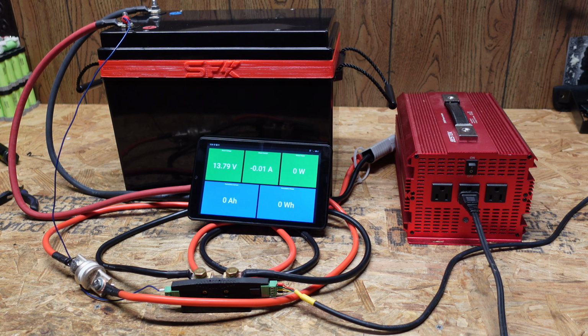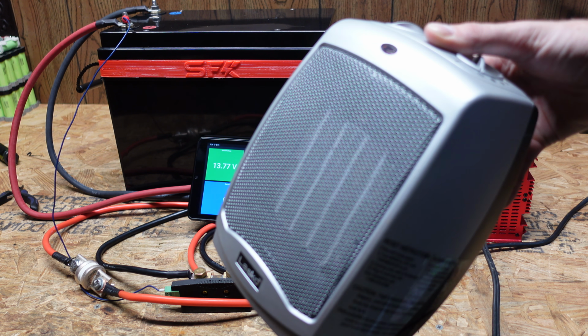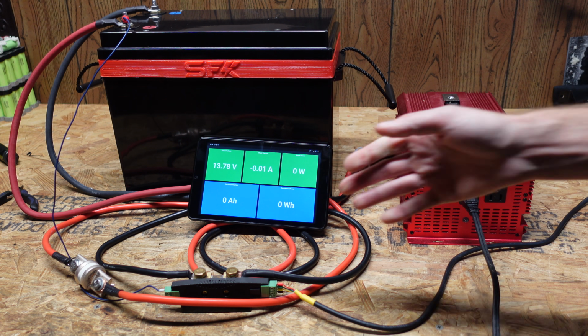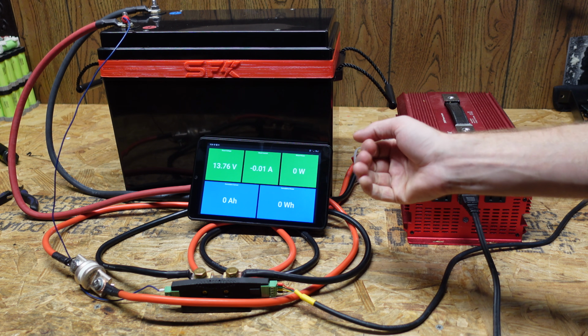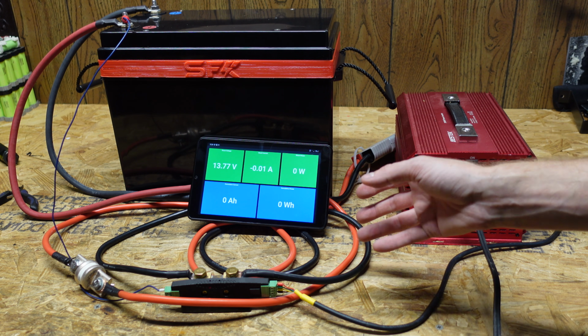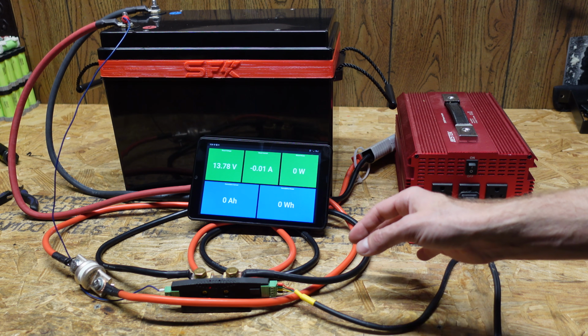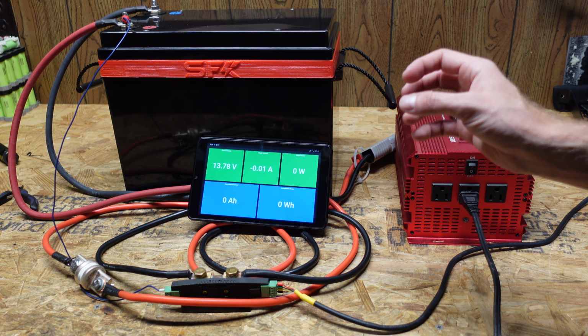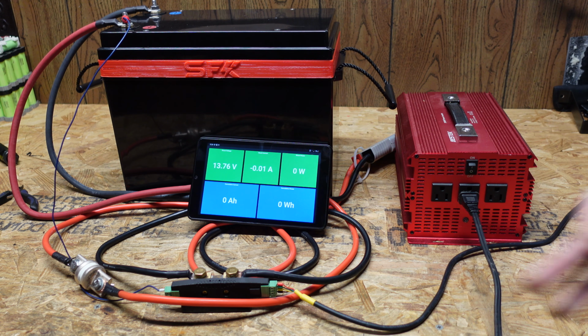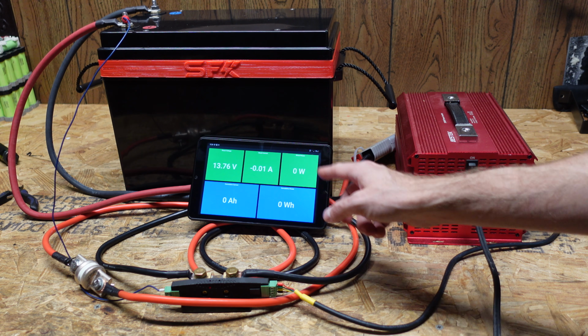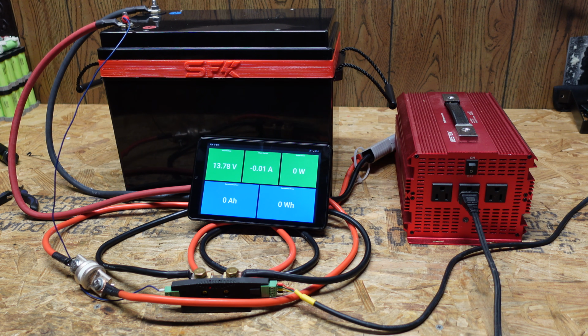For the load, I have a space heater. I'm going to run this on low, which should put approximately 975 watts on this battery, around a 0.27 C rate, I believe, when I calculated it out. We'll let this run until the inverter or the BMS shuts down, and we'll see what our capacity is. Here we go.